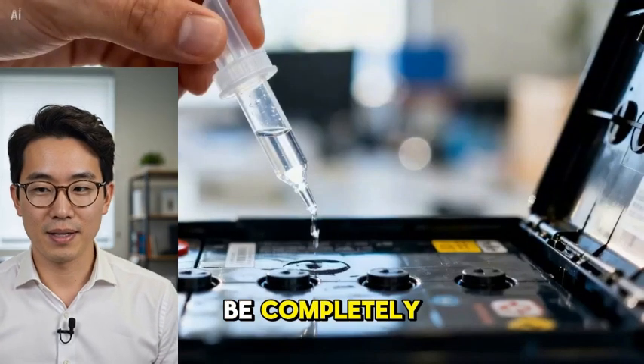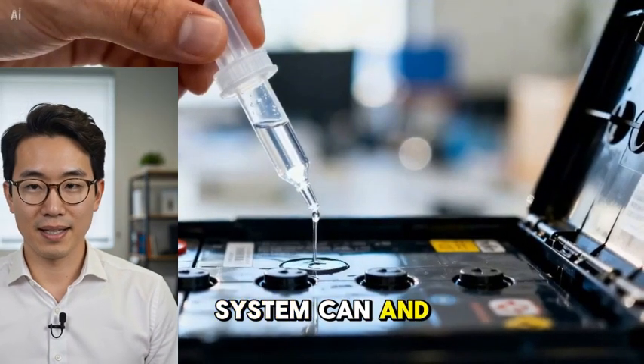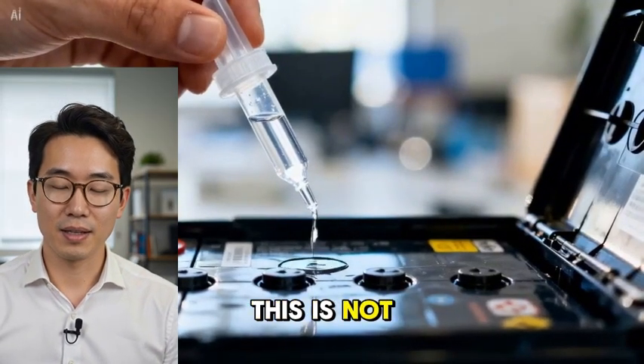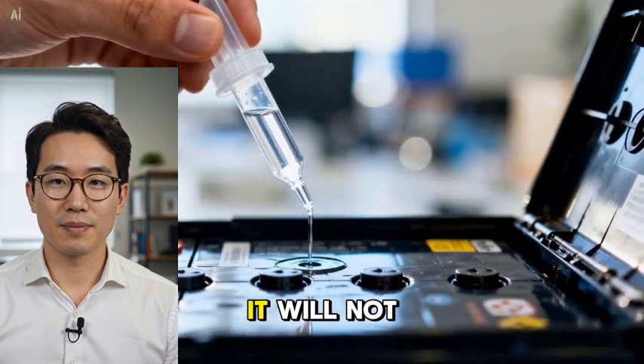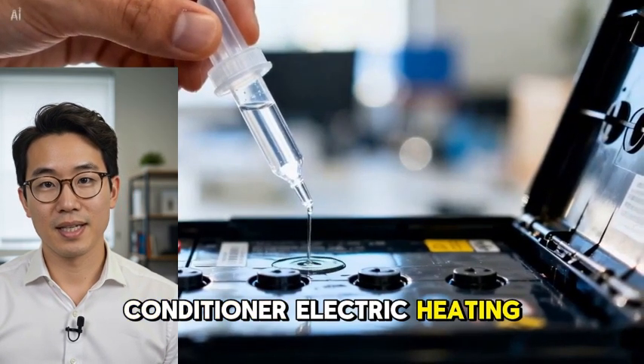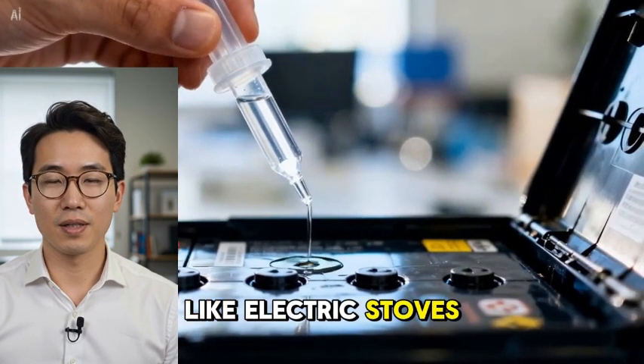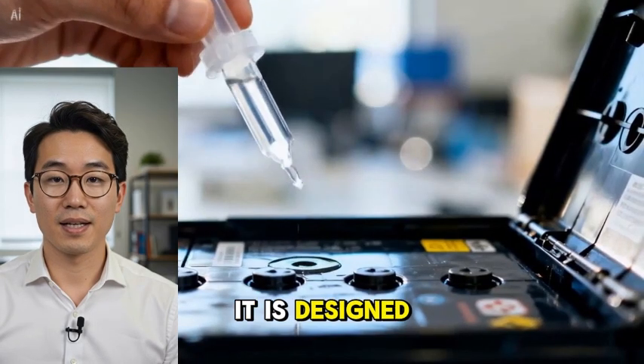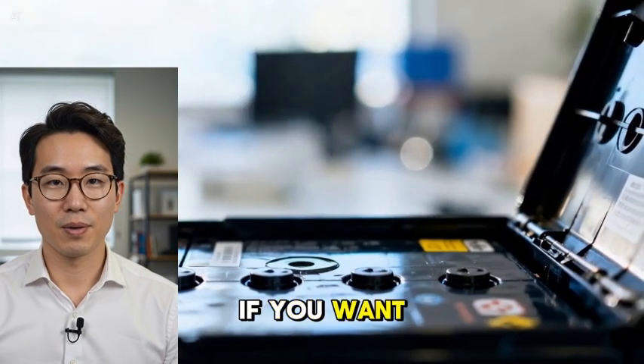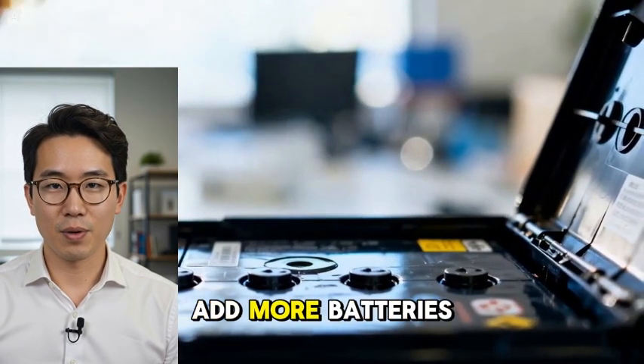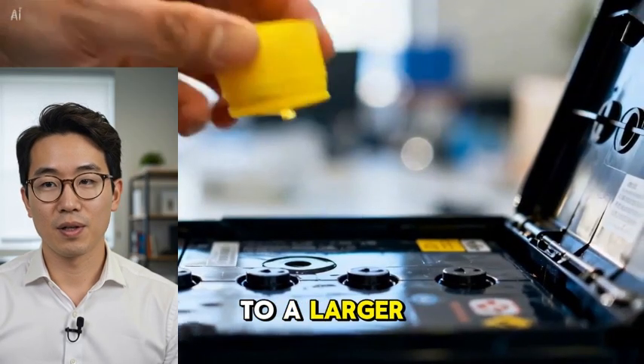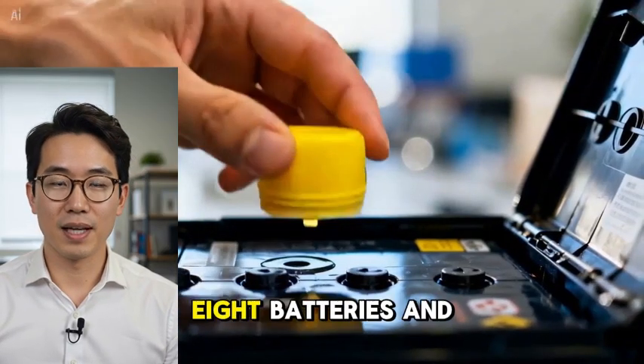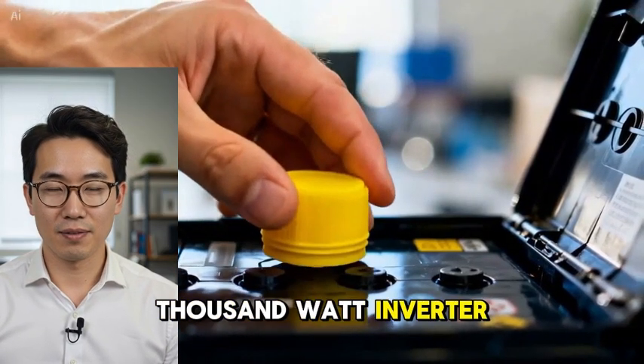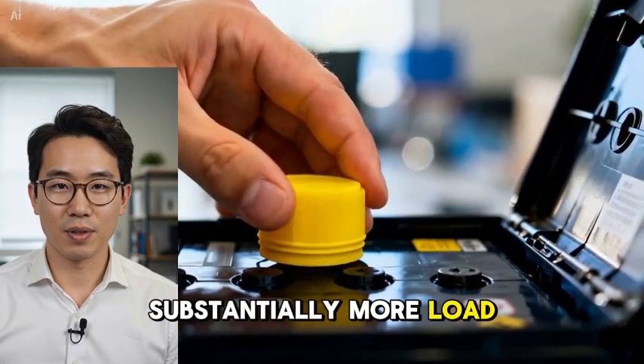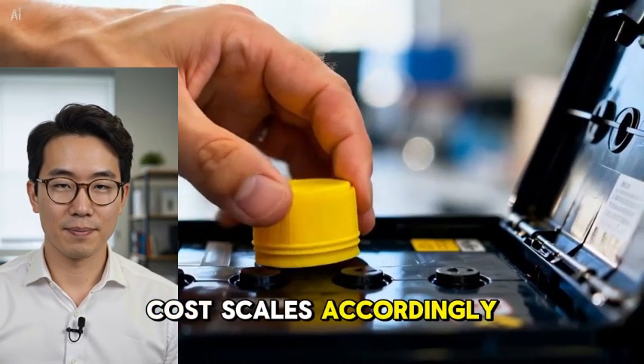I need to be completely transparent about what this system can and cannot do. This is not a whole home backup solution. It will not power your air conditioner, electric heating, or large appliances like electric stoves or dryers. It is designed for essential loads only. If you want to expand capacity, you can add more batteries in parallel and upgrade to a larger inverter. A system with 8 batteries and a 2,000 watt inverter can handle substantially more load, but the cost scales accordingly.